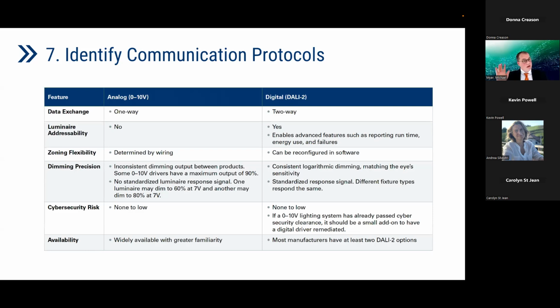Many people inherently think 0 to 10 has no cybersecurity risk. At the end of the day, 0 to 10 is really just communicating with the LED diodes, but you might have other communication systems in your building that need to be mitigated alongside the lighting system. So don't assume that because it's 0 to 10, there's no cyber mitigation needed—other communication modules may use protocols that still require it.